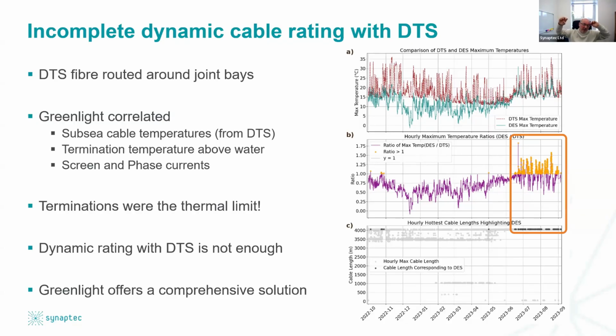Basically, what we noticed through the summer is that this cable was operating under sea, and the temperature of the cable itself was consistent, but the terminations were not underwater, they were up above the sea level in open air. And in the summer, they got very hot. And in fact, it was much hotter than the cable itself. In other words, the thermal limitation or ceiling of the system wasn't the cable, it was the termination. And if you can't see that termination with DTS, you don't know that's the weak point thermally where you've got a limitation, and you need to know what it is. So by applying our systems to contribute to the visibility of the whole, we've combined the DTS feed, which we supply the DTS boxes and the DTS information, and then you add the point temperature sensing on the terminations, and you can see that they were actually the thermal bottleneck. They were the limit. The cable was fine. It was the above air in the sunshine, getting very hot points that were actually causing the potential problem.